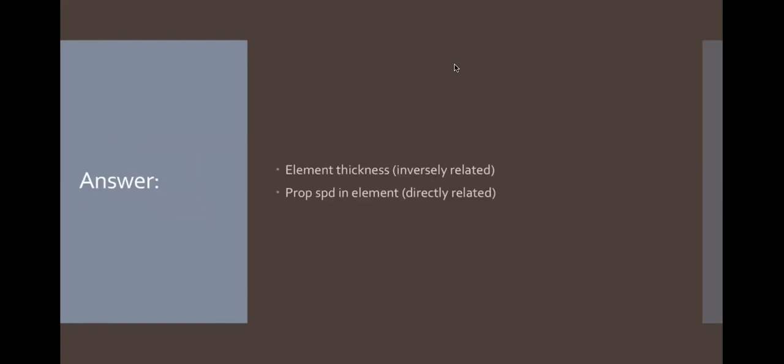Let me tell you something. Element thickness is not aperture. Aperture is element size, right? Sometimes students are like, well, isn't thickness and size the same thing? No, they're different dimensions. If I have a PZT that looks like this, or a PZT that looks like this, I'm talking about the size here. If I picked them up and flipped them to the side and looked at the thickness, the thickness is two different things, right?